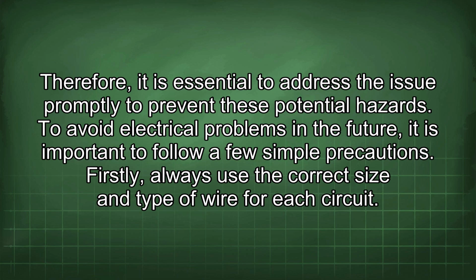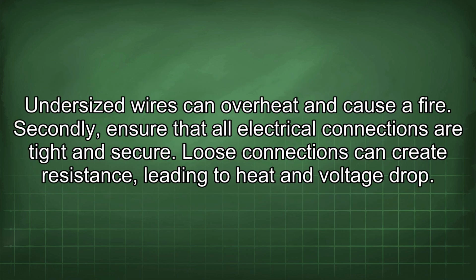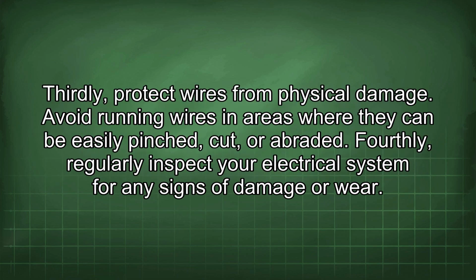To avoid electrical problems in the future, it is important to follow a few simple precautions. Firstly, always use the correct size and type of wire for each circuit. Undersized wires can overheat and cause a fire. Secondly, ensure that all electrical connections are tight and secure. Loose connections can create resistance, leading to heat and voltage drop. Thirdly, protect wires from physical damage. Avoid running wires in areas where they can be easily pinched, cut, or abraded.